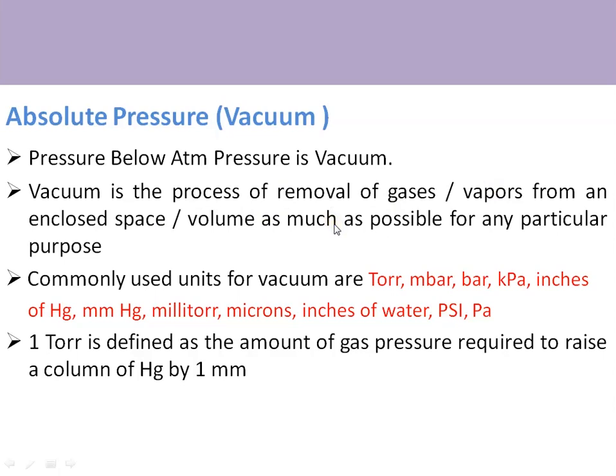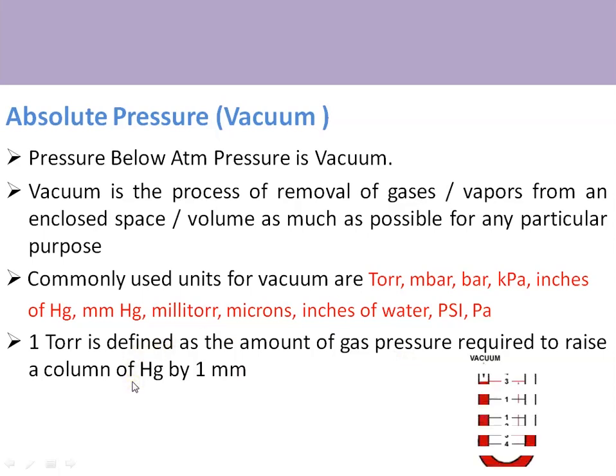Vacuum is the process of removal of gases or vapor from an enclosed space — such as containers, vessels, or furnaces — as much as possible for a particular purpose depending on the application. Commonly used units for vacuum are torr, millibar, bar, kilopascal, pascal, psi, and inches of water. The most commonly used unit is torr. One torr is defined as the amount of gas pressure required to raise a column of mercury by one millimeter, as seen in a U-tube manometer.